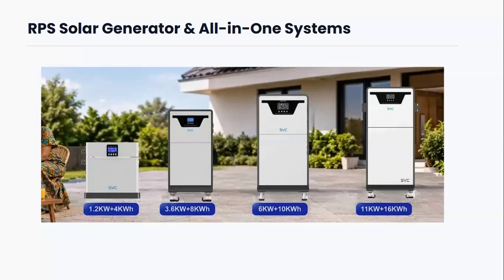Now, I know some people are still making mistakes in terms of this. They will say 1.2 kilowatts and want to make it look like it's the same thing as 4 kilowatts. No, somebody may say, okay, 1.2 kilowatts capacity of inverter, then 4 kilowatts capacity of battery - that means the battery capacity is bigger than the inverter capacity. It's not like that. That's why battery is rated in kilowatt hour - it's a storage, talking about the capacity of load it can power and the duration it can power the load. So they are not exactly the same thing, like in a generator or any other source of supply.